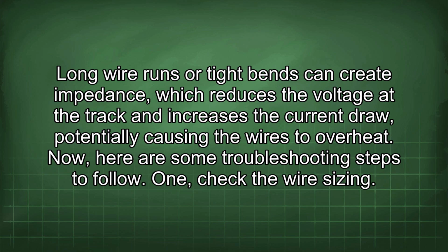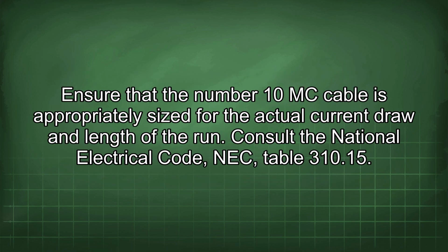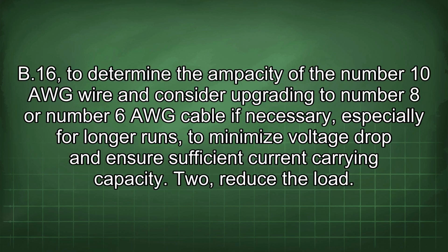1. Check the wire sizing. Ensure that the number 10 MC cable is appropriately sized for the actual current draw and length of the run. Consult the National Electrical Code, NEC, Table 310.15(B)(16) to determine the ampacity of the number 10 AWG wire and consider upgrading to number 8 or number 6 AWG cable if necessary, especially for longer runs, to minimize voltage drop and ensure sufficient current carrying capacity.